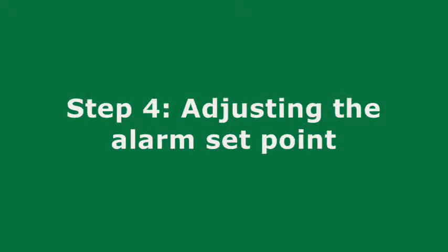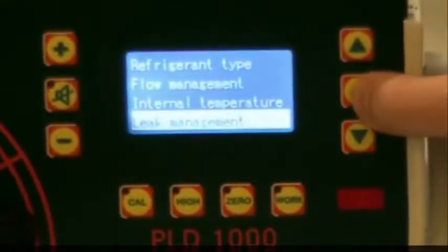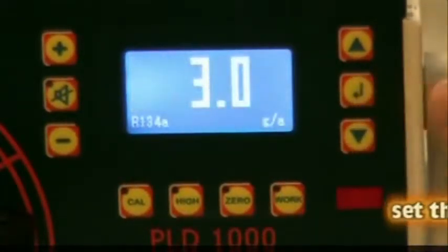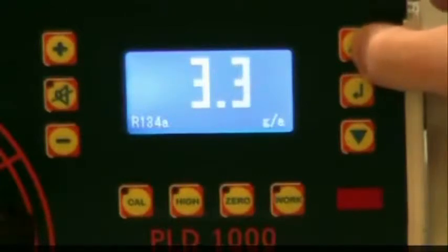Step 4: Adjusting the Set Point. To adjust the leak set point, press the Enter key and select Leak Management. Use the arrow keys to adjust the alarm threshold.